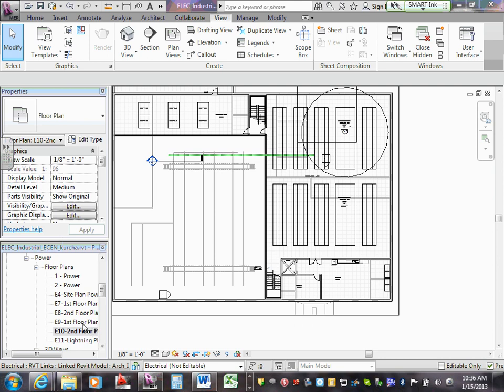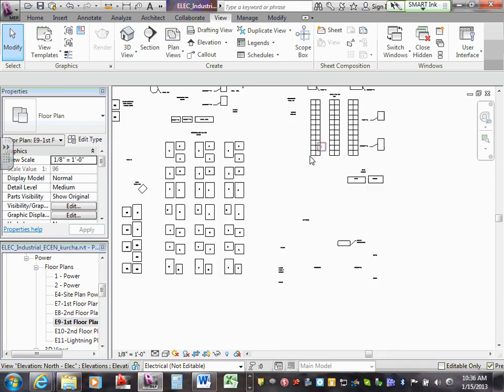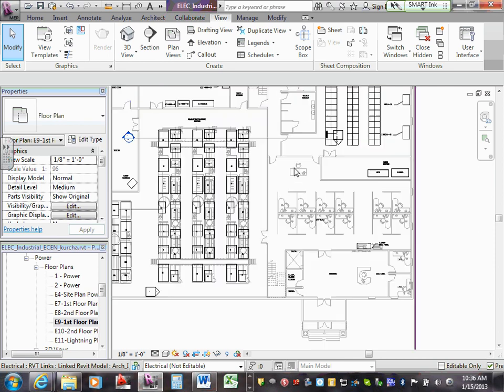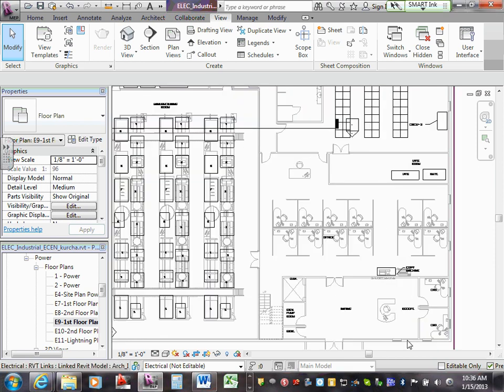That's good. First floor in the office area, you're gonna space your horn strobes every 50 feet on the center. So you just pick a corner, 25, 25 for your first one, you're gonna be 50 feet. Ceiling mount, yep.